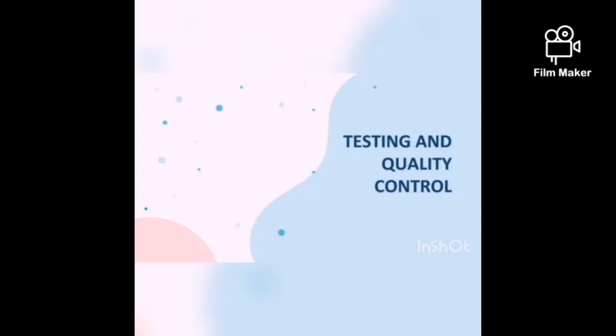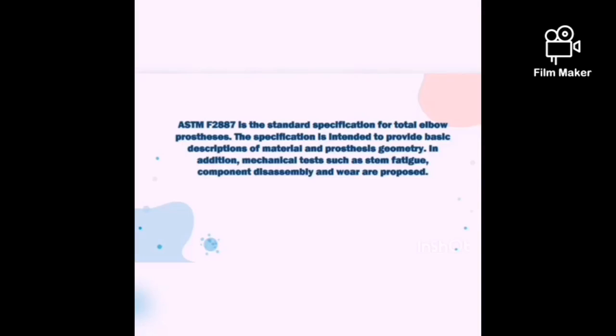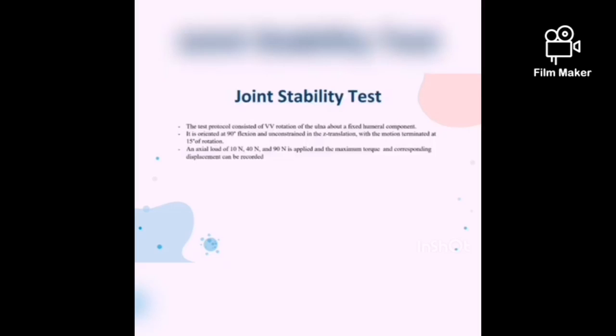Now that we are done with the effects of parameters, let's move to the testing and quality control. The standard specification for total elbow replacement is ASTM F2887. The specification is intended to provide basic descriptions of material and prosthesis geometry. To make sure the implant is working well, a few tests need to be done.